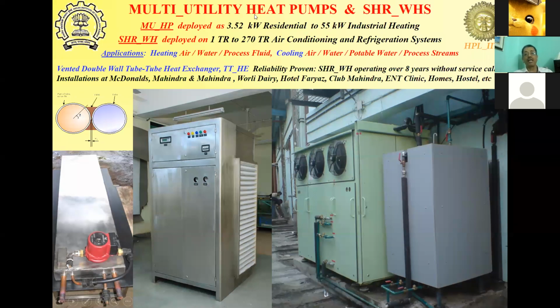Water heaters. We have developed technologies right from residential applications of 1 ton or even lower than 1 ton, all the way up to 12 tons capacity in a single module and up to 24 tons for larger multiple compressor based systems. We have superheat recovery systems deployed from 1 ton application to 270 ton in a dairy. And even if a 3,000 ton application comes up, we won't have a hesitation in taking up the project based on this. So what are the applications?